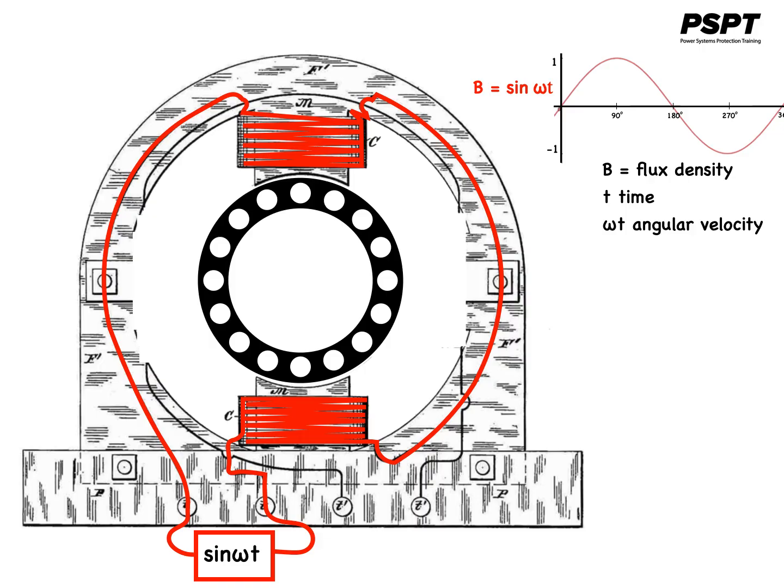However, once the rotor begins to turn, an induced torque will be produced in it. If the rotor of a single-phase motor is rotated in one direction by some mechanical means, it will continue to run in that direction of rotation. As a matter of fact, the rotor quickly accelerates until it reaches a speed slightly below synchronous speed. Once the motor is running at this speed, it will continue to rotate even though single-phase current is flowing through the stator winding. This method of starting is generally not convenient for large motors.